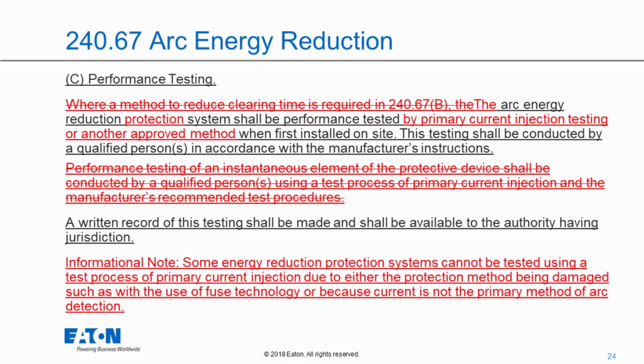But what happened is when they finished the second draft of the NEC, they realized that they had an error here. They required that you must use primary current injection testing as the only option to test this equipment. And they realized that there are a variety of different reasons why you would not want to use primary current injection testing. So they basically did a TIA before the code even came out. They did a TIA that corrected this issue. And so now they basically require you to do testing of the arc energy reduction protection system, but you can use primary current injection where it makes sense or another approved method. And here's the real key thing here. It says this testing shall be conducted by a qualified person in accordance with manufacturer's instructions. And that's really what I want to draw to your attention.